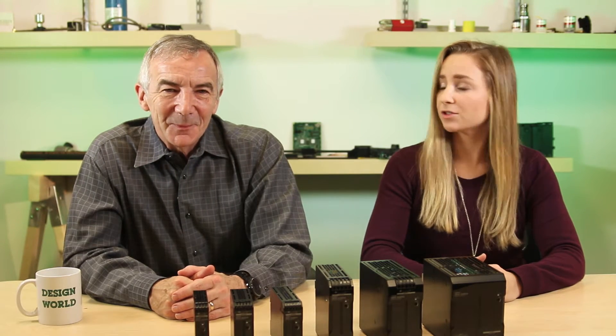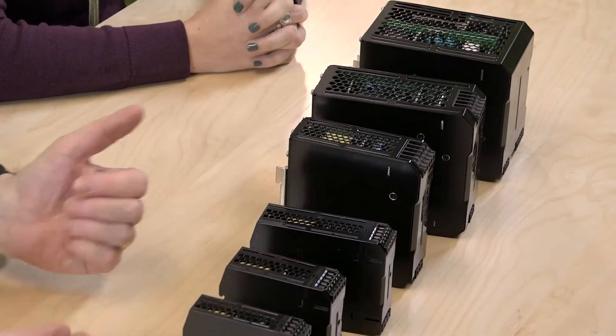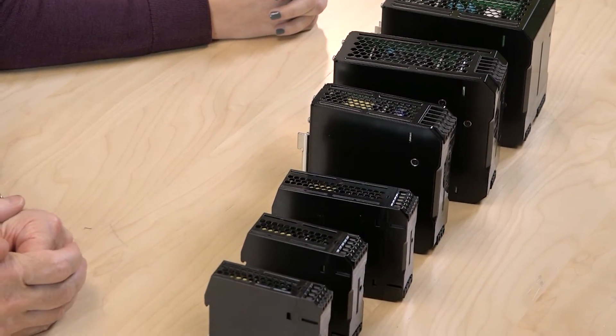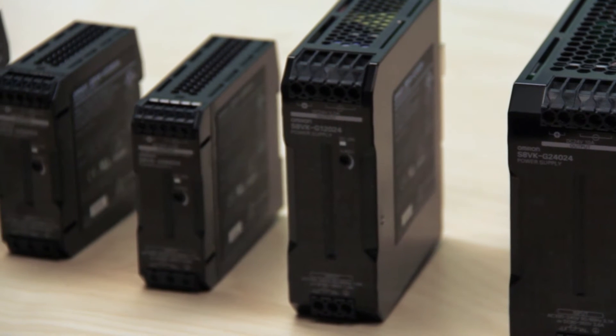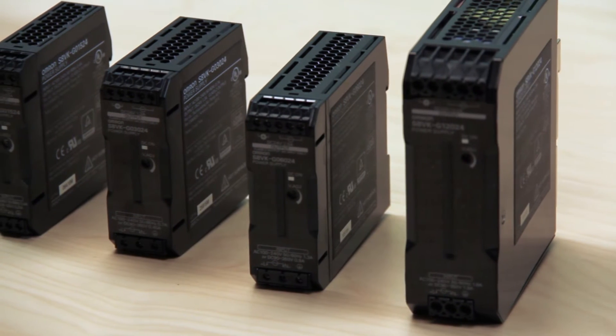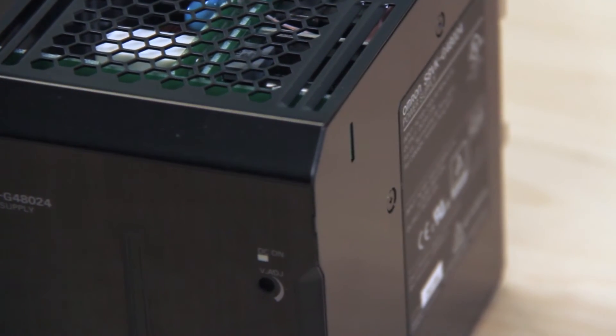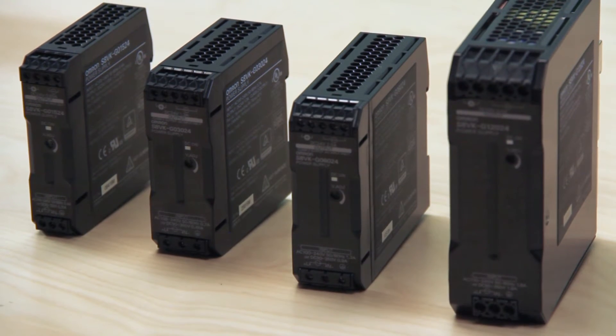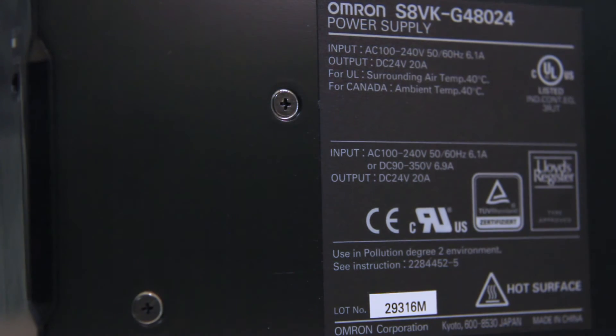These supplies have a lot of specifications. These are industrial supplies, so they have an industrial operating temperature range and models are available with conformal coatings for harsh environments such as corrosion, humidity, or dust. Depending on the supply, they also produce output currents ranging from 650 milliamps to 24 amps, and they have built-in overload and over-voltage protection.